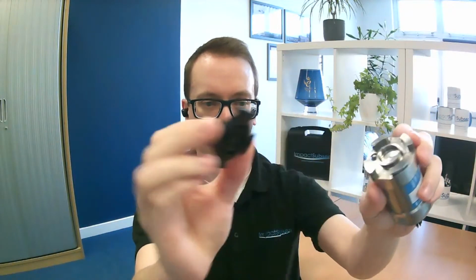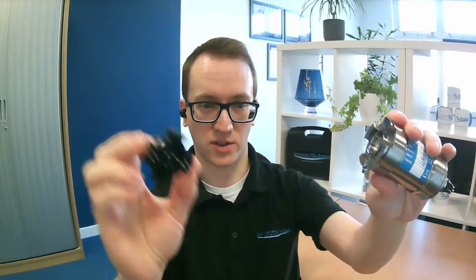And on the other end, you've got a plastic cover, which covers the raw pressure sensor and also the temperature sensor just in there. Both of these can be accessed by removing the black plastic cap. You can do that by the little clip there. You can get your finger in there and just prise the clip apart. The clip comes off, and then the protective end cap comes off and away.